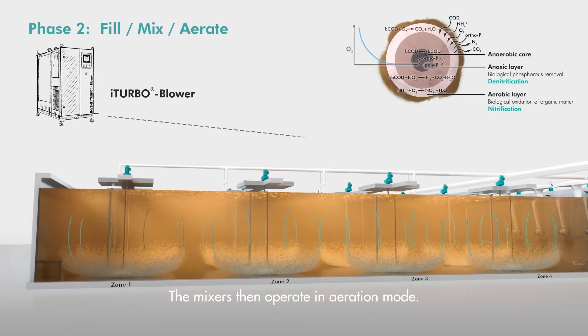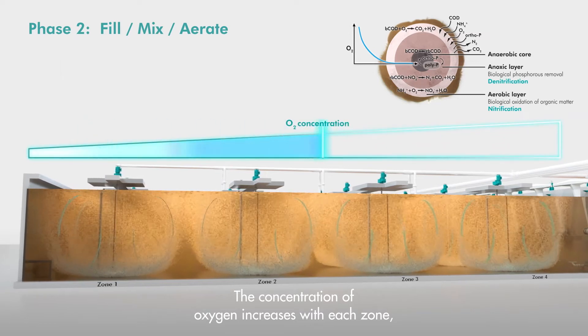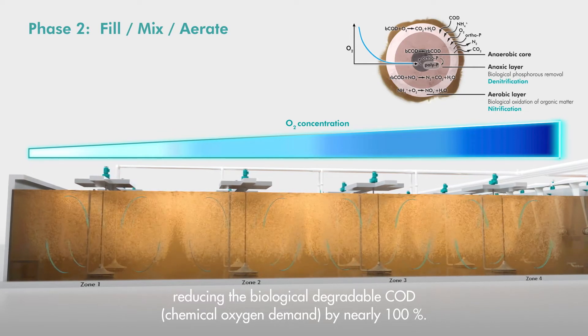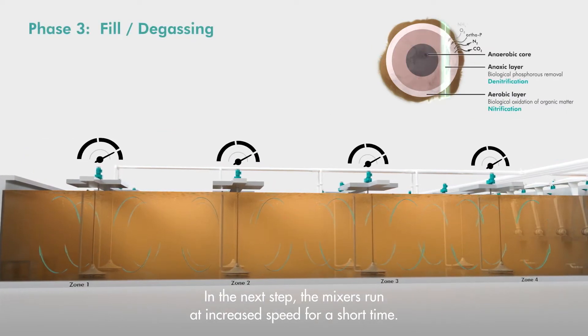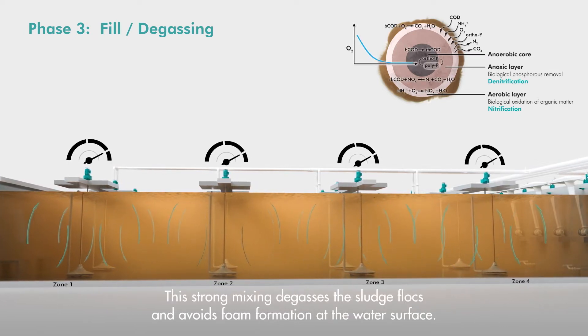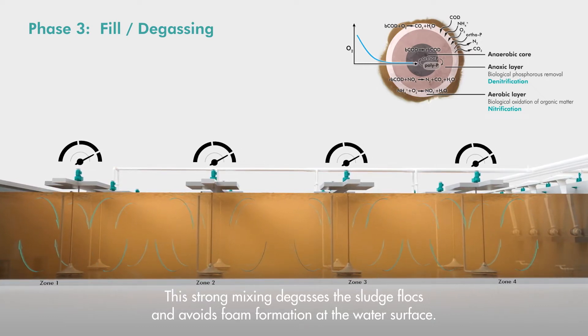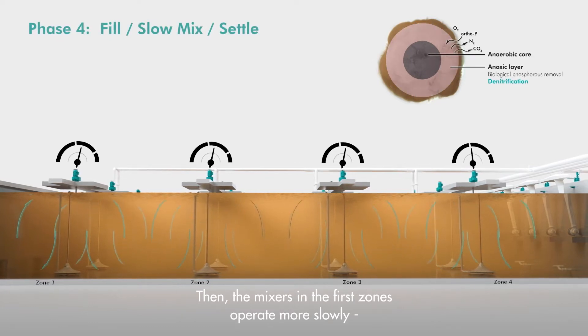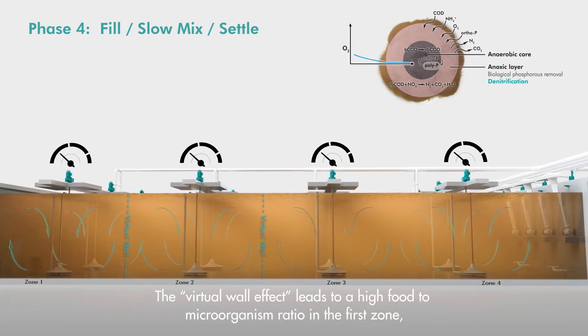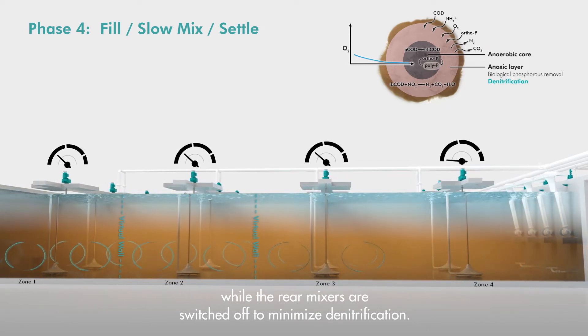The mixers then operate in aeration mode. The concentration of oxygen increases with each zone, reducing the biologically-degradable chemical oxygen demand by nearly 100%. In the next step, the mixers run at increased speed for a short time. This strong mixing degases the sludge flocs and avoids foam formation at the water surface. Then the mixers in the first zones operate more slowly. The virtual wall effect leads to a high food-to-microorganism ratio in the first zone, while the rear mixers are switched off to minimize denitrification.